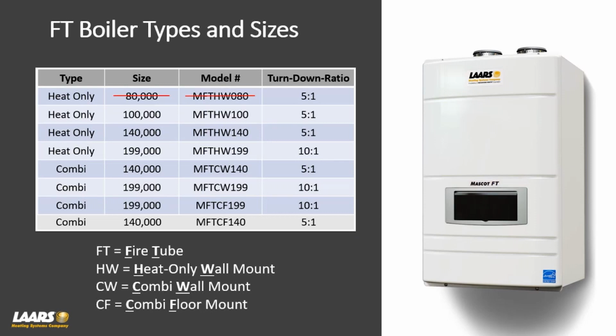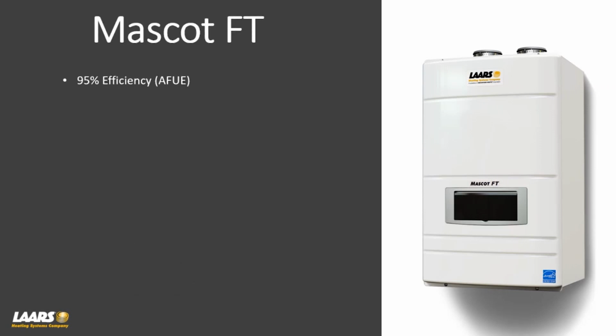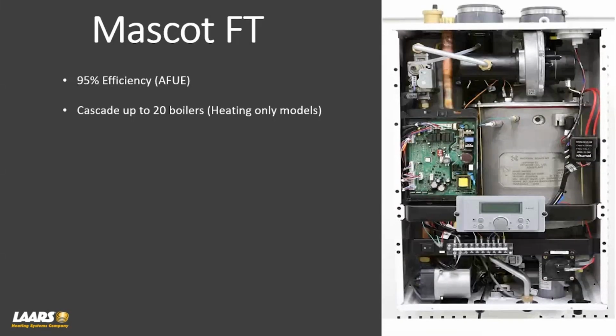Now, all of these are going to be a 5-to-1 turn down ratio on your modulation, other than the 199. The 199 is a 10-to-1 turn down. So an example of that, 199,000, it'll modulate all the way down to 19,900 BTUs. Up to 95% efficient, we'll go over outdoor reset and how your efficiency values change as your return water temperature becomes cooler. We get higher efficiencies that way. We can cascade up to 20 heating only models. Okay, so 20 boilers can be cascaded on the heating only models. We have ASME H stamping right on the nameplate.